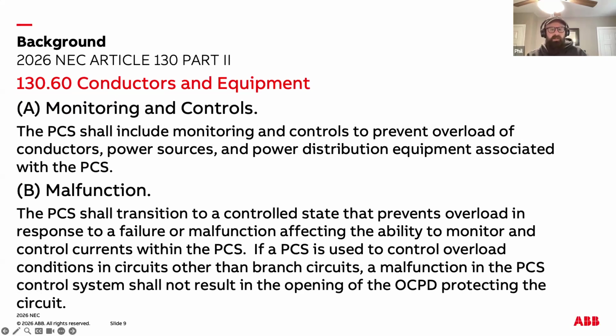130.60, new to the 2026 NEC, establishes how a PCS must perform in order to be recognized as a system capable of preventing overload. Because PCS is allowed to influence load calculations and conductor sizing, the code requires that these systems meet specific, verifiable performance criteria. PCS must continually monitor electrical parameters, typically current, power, or both, to detect when loads or sources approach the limits of the protected conductors or equipment.